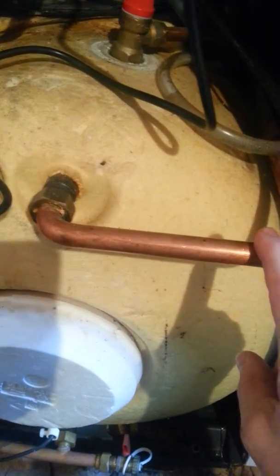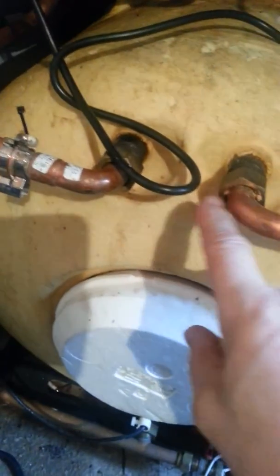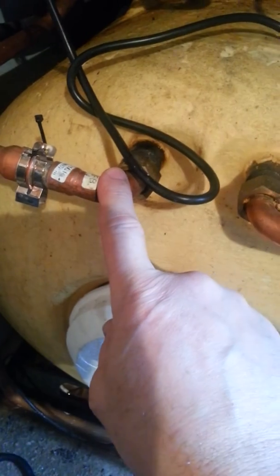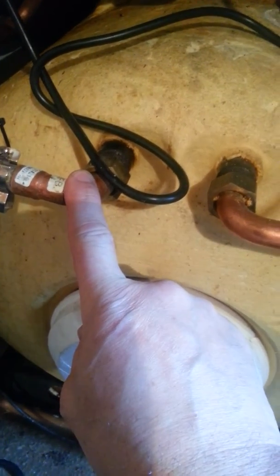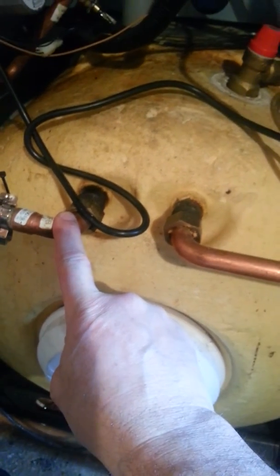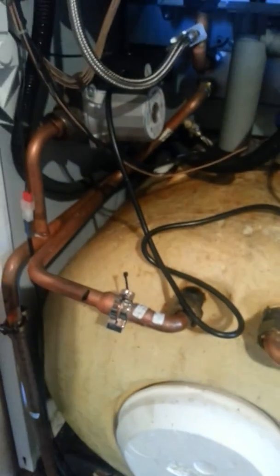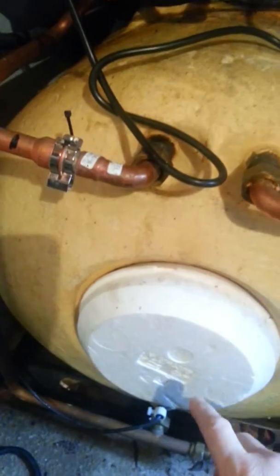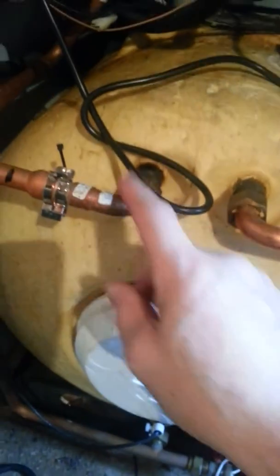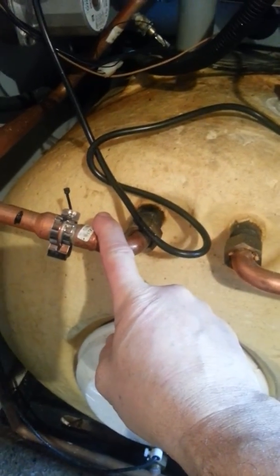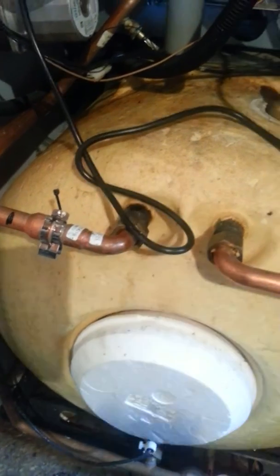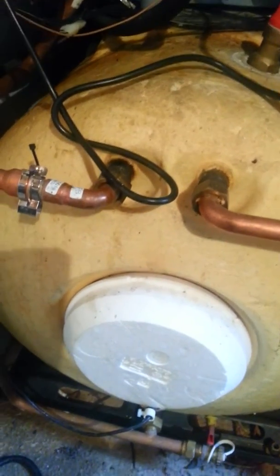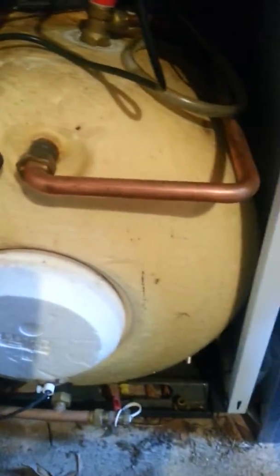Now that can be drawn off quite rapidly, perhaps 20 litres, maybe even more per minute, but it's still only being reheated at the rate of a combi boiler, and in fact on this boiler I've noticed it never fires at full rate when it's reheating during operation, so it's not even the full rate of the boiler. So once this small cylinder is exhausted, you can basically turn your bath taps down to the usual combi boiler trickle and you're back in combi boiler mode, which is great if you just want to rapidly fill one bath.